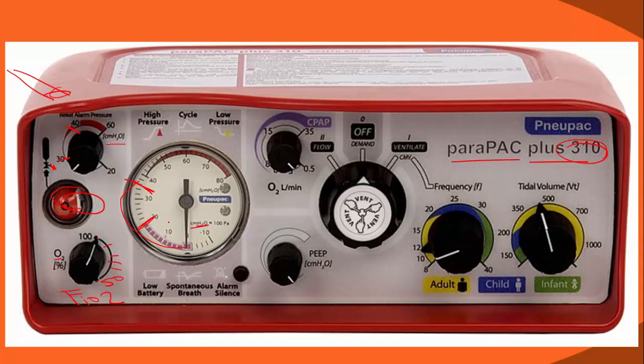We really want to be around 20, and this will move every time ventilation is administered and then go back down. If it doesn't go back down, if it maintains high, then we probably have either PEEP set or some problem in the tubing. Moving to the next set here, and then of course there's some alarms here: battery, the patient took a spontaneous breath. And this button here silences the alarm, but never silence the alarm until you figure out what's wrong with your device.